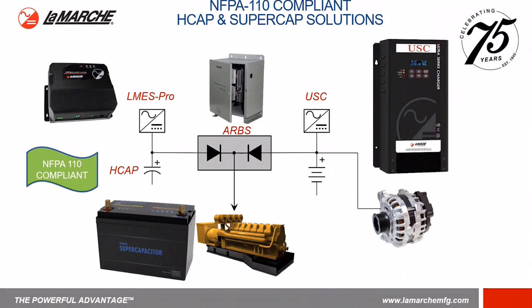And here's a diagram of the NFPA compliant system where one of the sources you have the HCAP. On the other side, you have your traditional NiCad or lead acid batteries that NFPA mentions. We are currently working with NFPA to get the HCAP as an approved battery storage system. And the nice thing about this solution, the HCAP provides the short duration current that an engine may require, while the batteries have the long duration. This will also extend your battery life on the lead acid and NiCad because most of the short-term current power will come from the HCAPs.